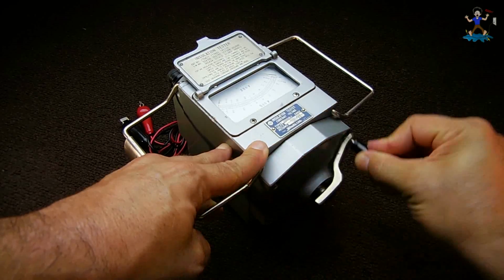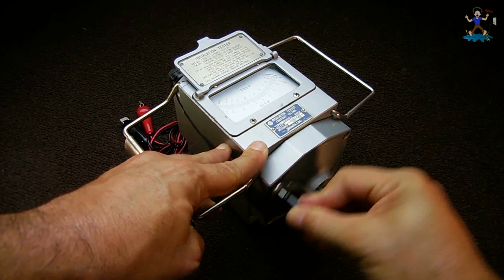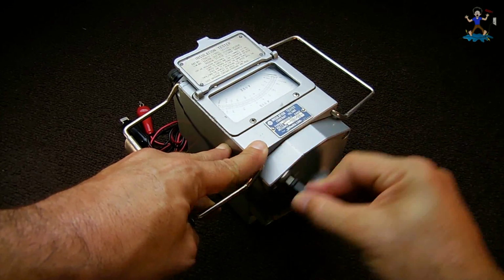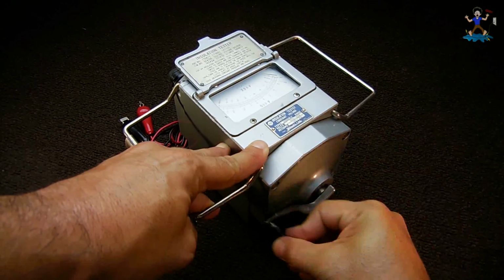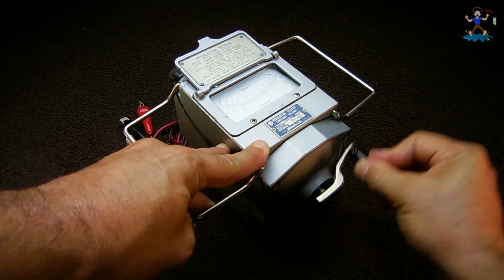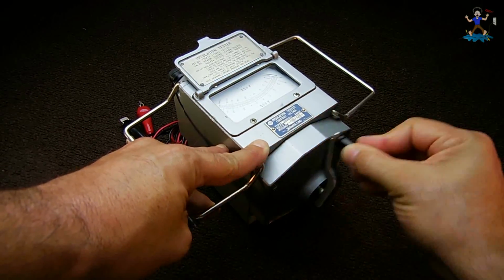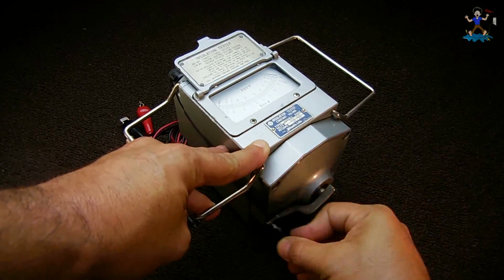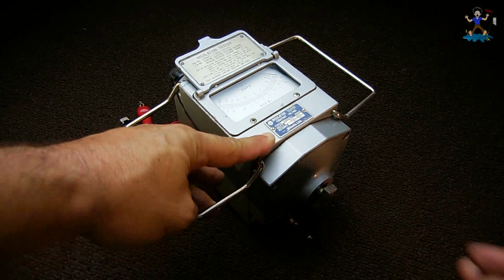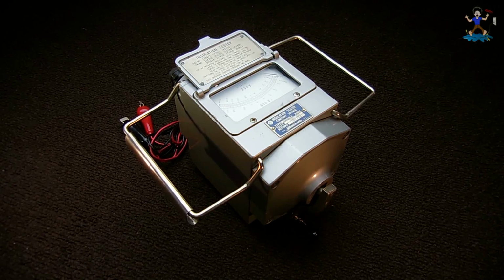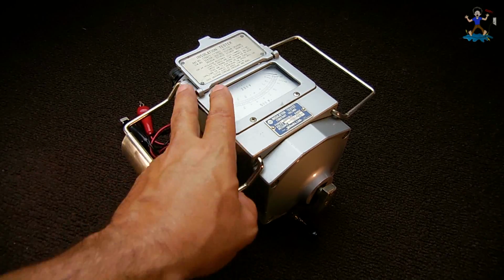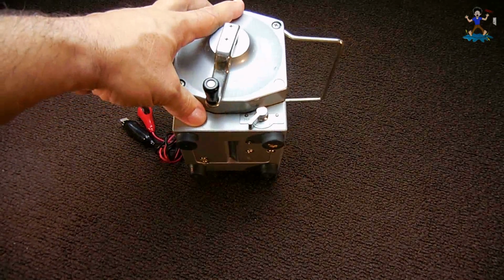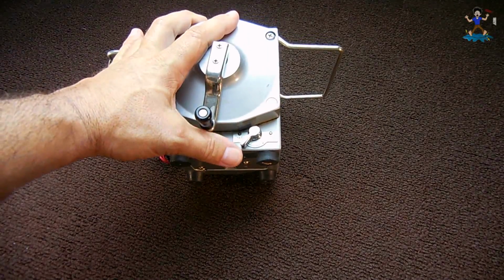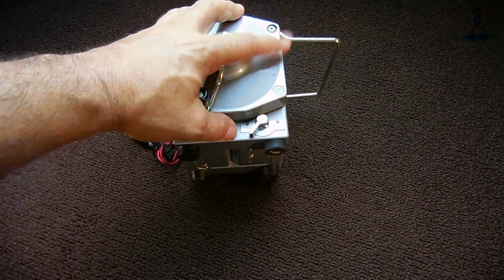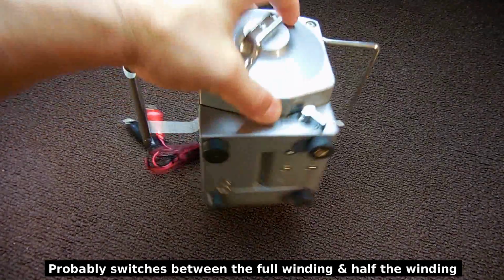And you can hear it slipping right now. Now it's normal. See, it's slipping, the handle's spinning faster, but the generator itself is not going faster. And that is how this particular type is designed. On the bottom, you have a selector switch, 250 volts or 500. Look at the bottom.